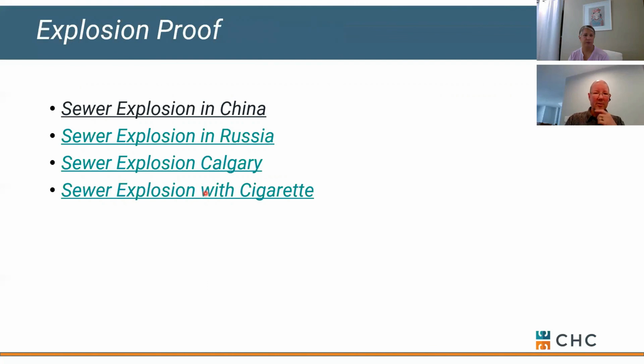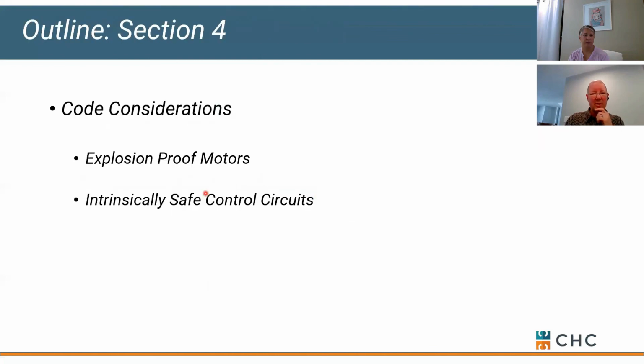And before I get to this quick video, one thing I didn't touch on is intrinsically safe controls. Most of our floats run at 120 volts, but if you're doing explosion-proof, we reduce that down to about 24 volts, which we call ISR, or intrinsically safe relays. It's just lower voltage, less potential for a spark.